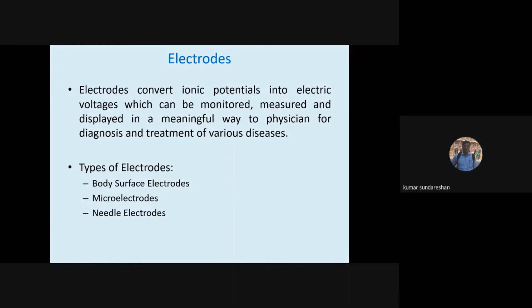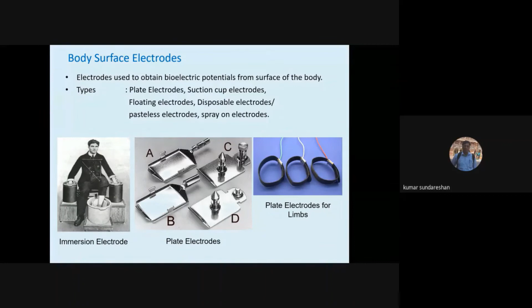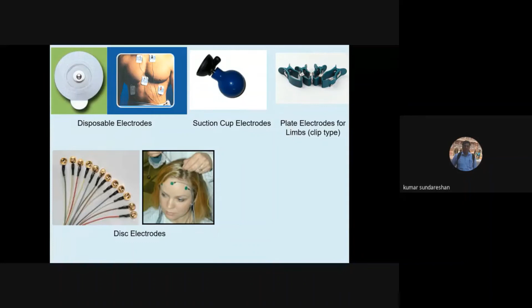So not only by knowing about the surface electrodes, but also we need to understand from the application perspective what kind of electrodes are used for picking up a different set of bioelectric signals. We have disposable electrodes, suction cup electrodes, again the limb electrodes, the clip type, disc electrodes. So all these basically are surface electrodes. So the suction cup is primarily used, as you are aware, along with the limb electrodes and disposable electrodes for picking up electrocardiogram. Then you have the disc electrodes or the cup electrodes, which are used to pick up electroencephalogram.